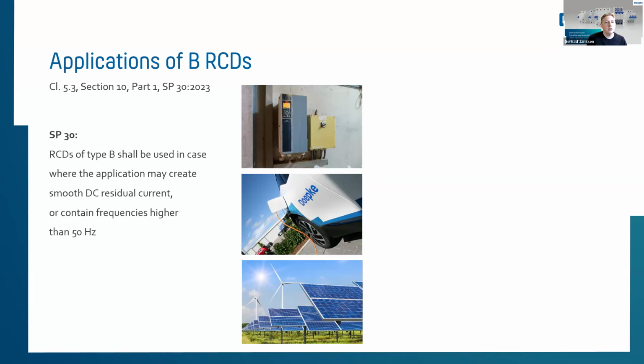Again, as Chris said, it will not be the cheapest solution, but it will be the safest solution. Cheap and safety sometimes do not go hand in hand. But the safest protection against fire risk, and even the protection of humans, can be done with a type B. So RCDs of type B shall be used where the application may create smooth DC or direct DC residual currents, or contain frequencies higher than the normal 50 cycles grid. So keep in mind three-phase applications with frequency drives, direct DC currents, or where the normal frequencies are unequal to 50 cycles.